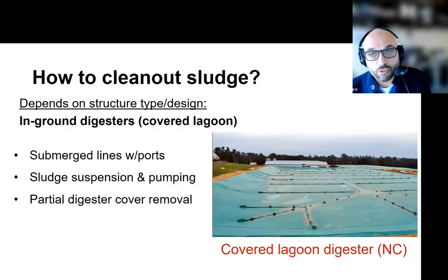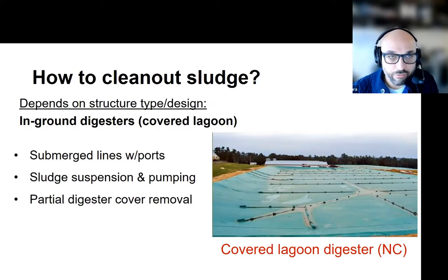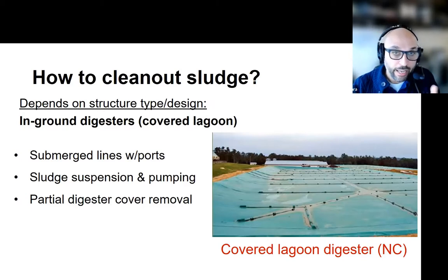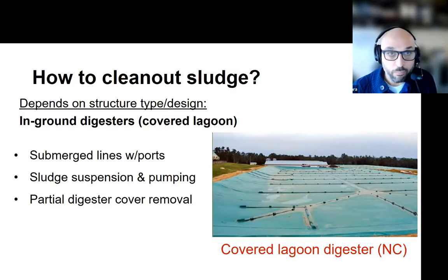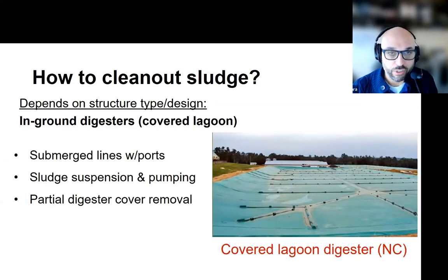When we move into a covered structure - using the covered lagoon as an example - accessibility of the sludge is the primary barrier. Generally, before adding covers to lagoons or covered digesters, installing submerged lines with ports at uniform distances to allow for pumping out this material is important. Alternatively, installing plumbing at different points where high horsepower suspension pumping would be required to slurry the digester before pumping out the sludge. Or if both fail, a partial or complete removal of the cover to recover the sludge similar to what we've seen in open lagoons.